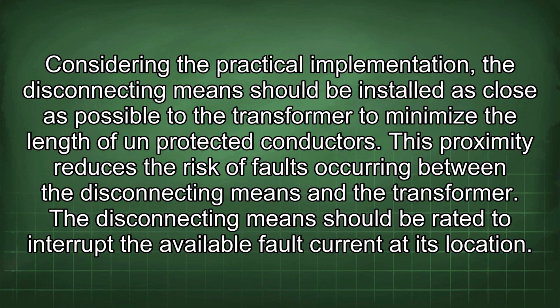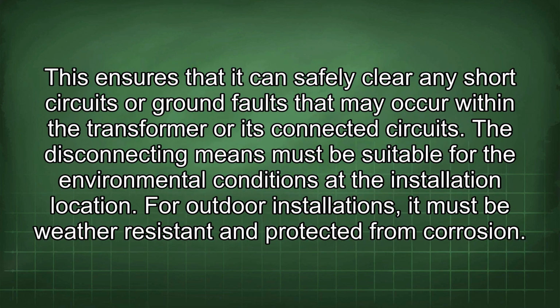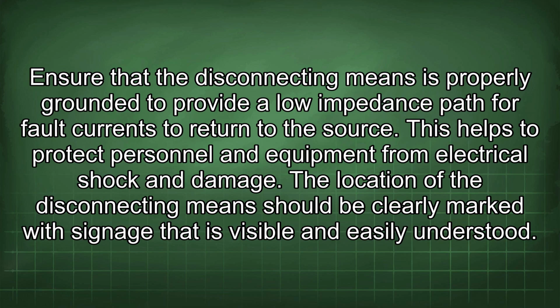The disconnecting means should be rated to interrupt the available fault current at its location. This ensures that it can safely clear any short circuits or ground faults that may occur within the transformer or its connected circuits. The disconnecting means must be suitable for the environmental conditions at the installation location. For outdoor installations, it must be weather resistant and protected from corrosion. Ensure that the disconnecting means is properly grounded to provide a low impedance path for fault currents to return to the source. This helps to protect personnel and equipment from electrical shock and damage.